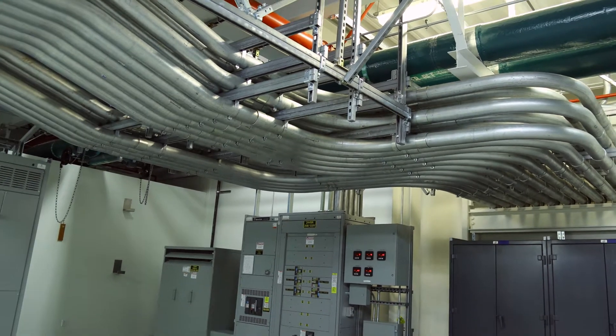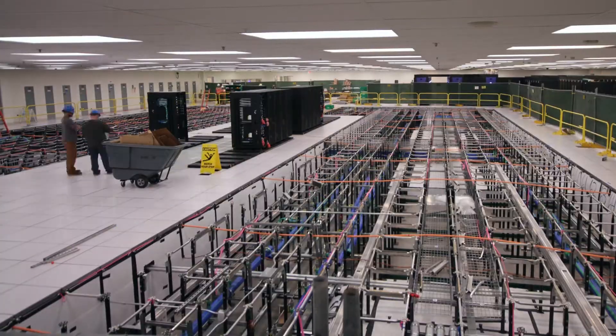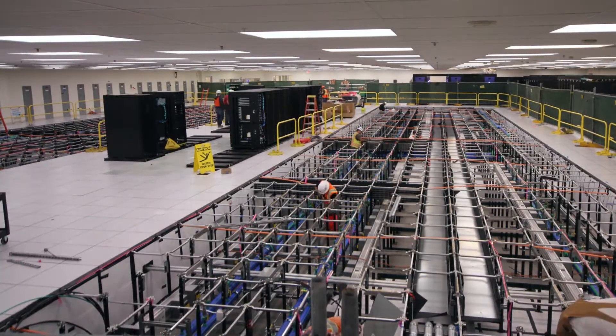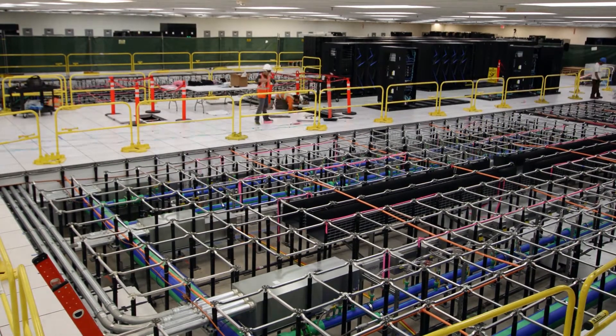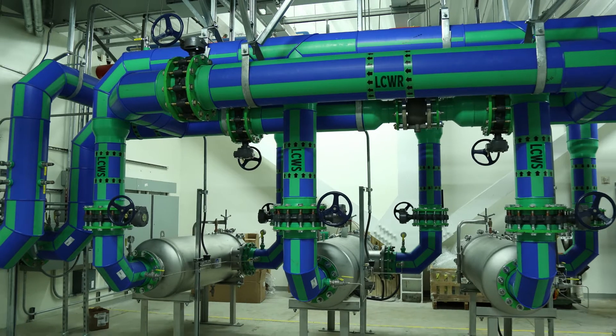It's the first time that we're distributing this amount of power in a small area. We have new 2.5 megawatt power transformers that will bring higher voltage to the dense Sierra racks. To distribute that power, we're using underfloor busway for the first time, rather than the conventional subpanels that are against the wall.